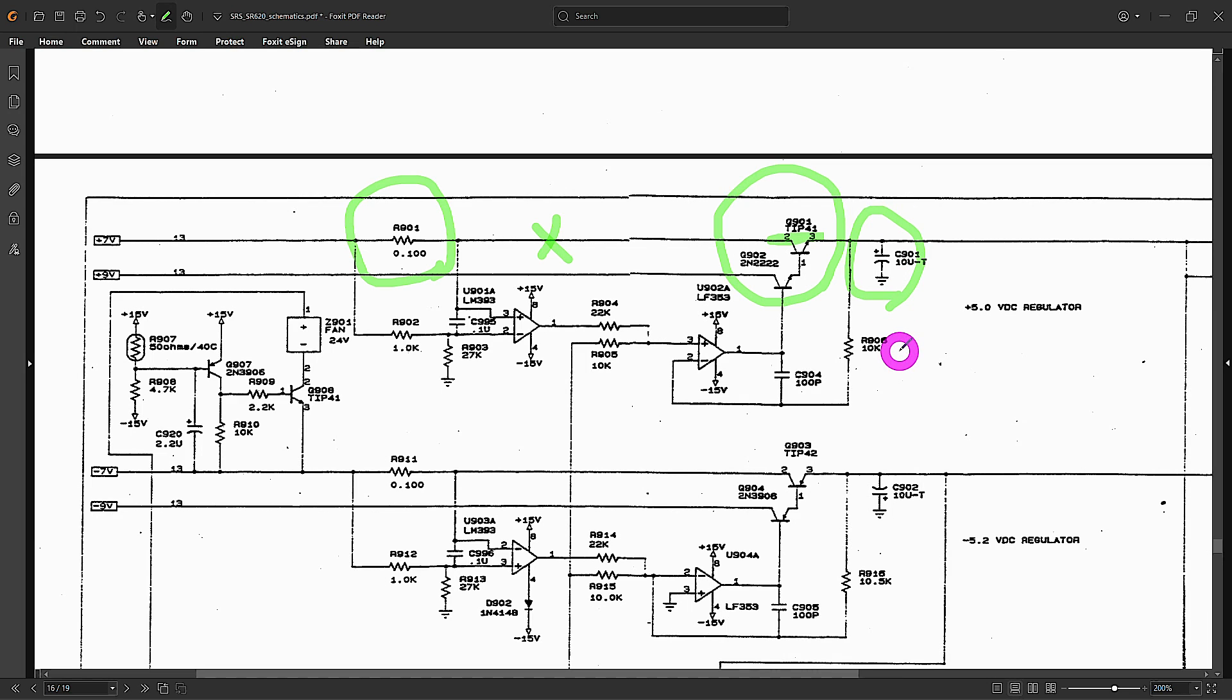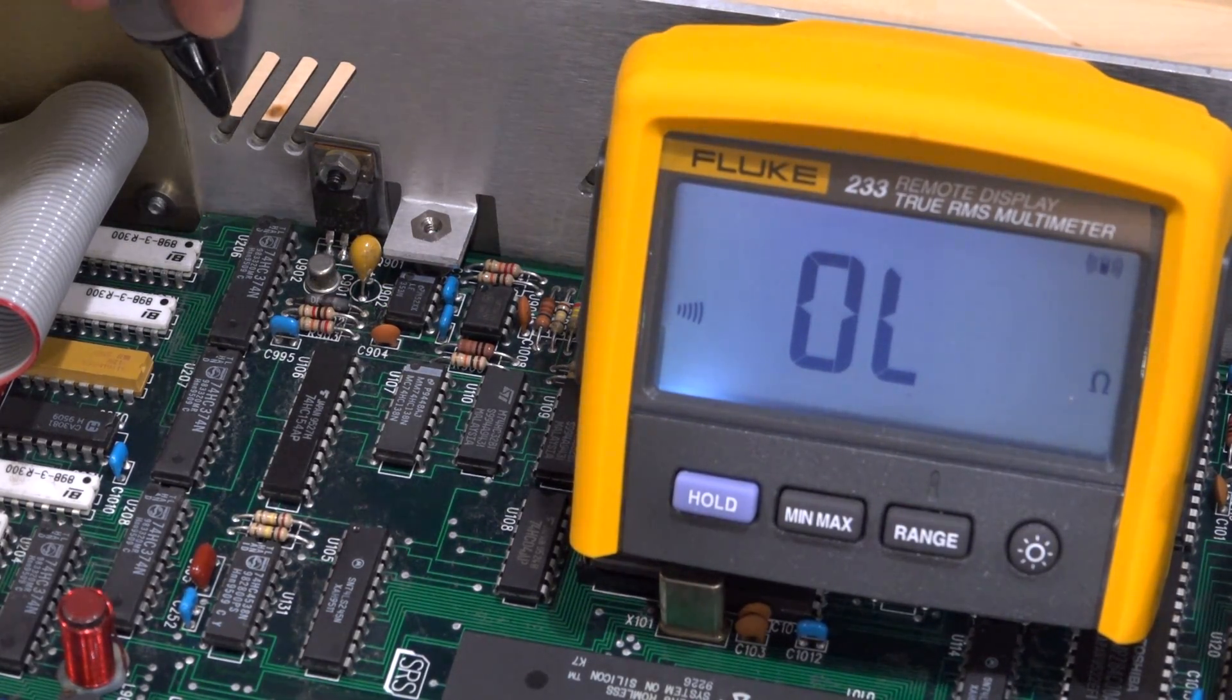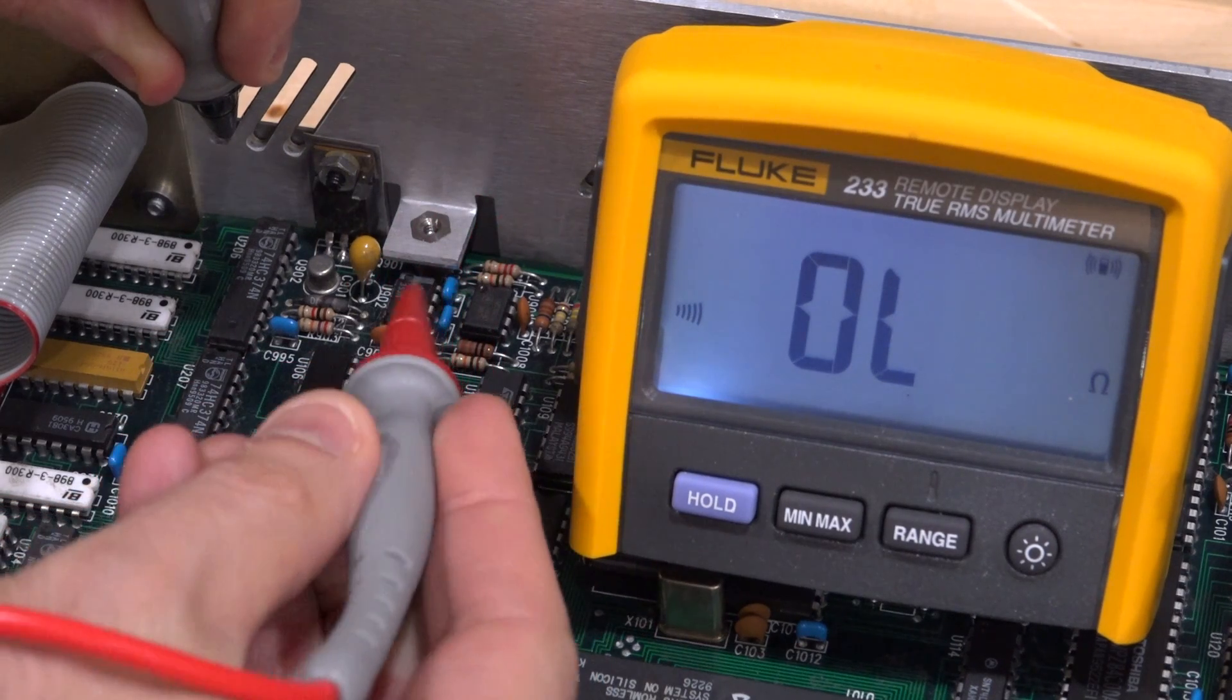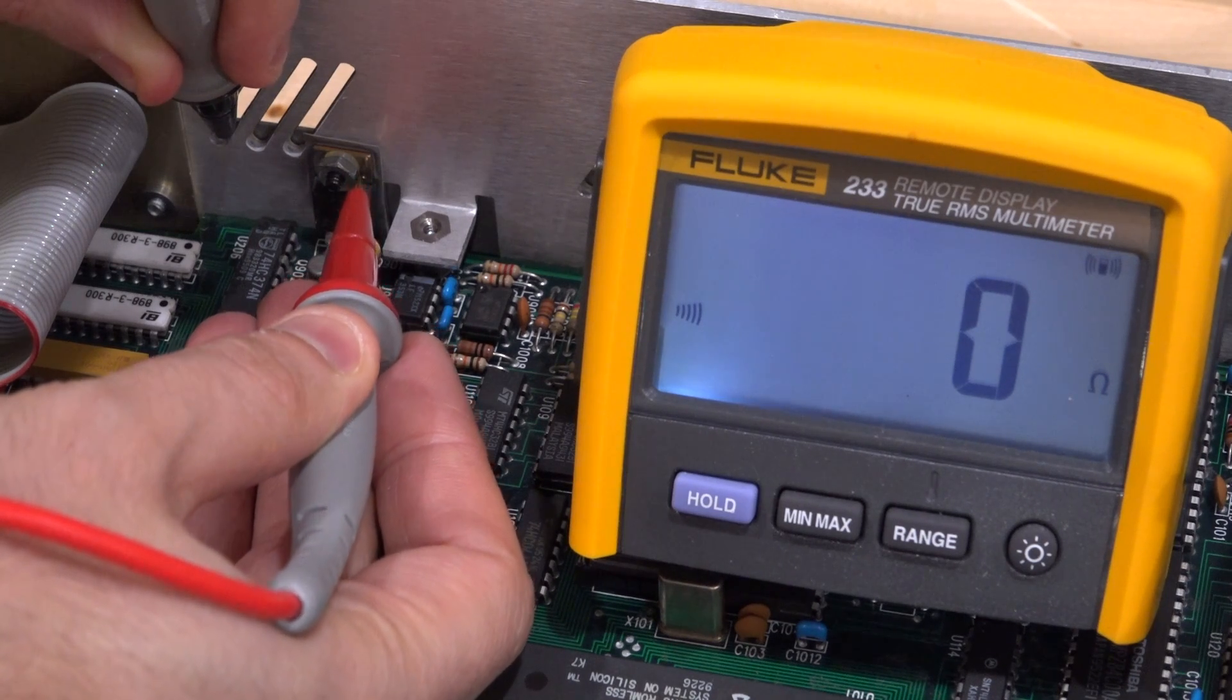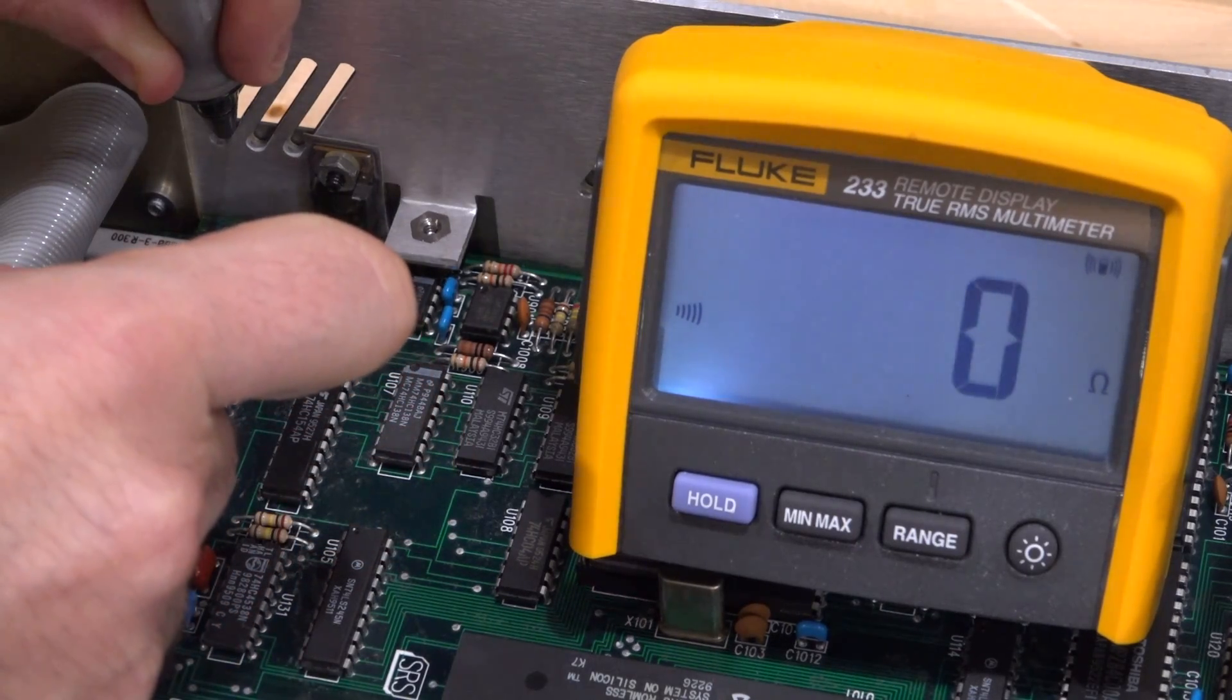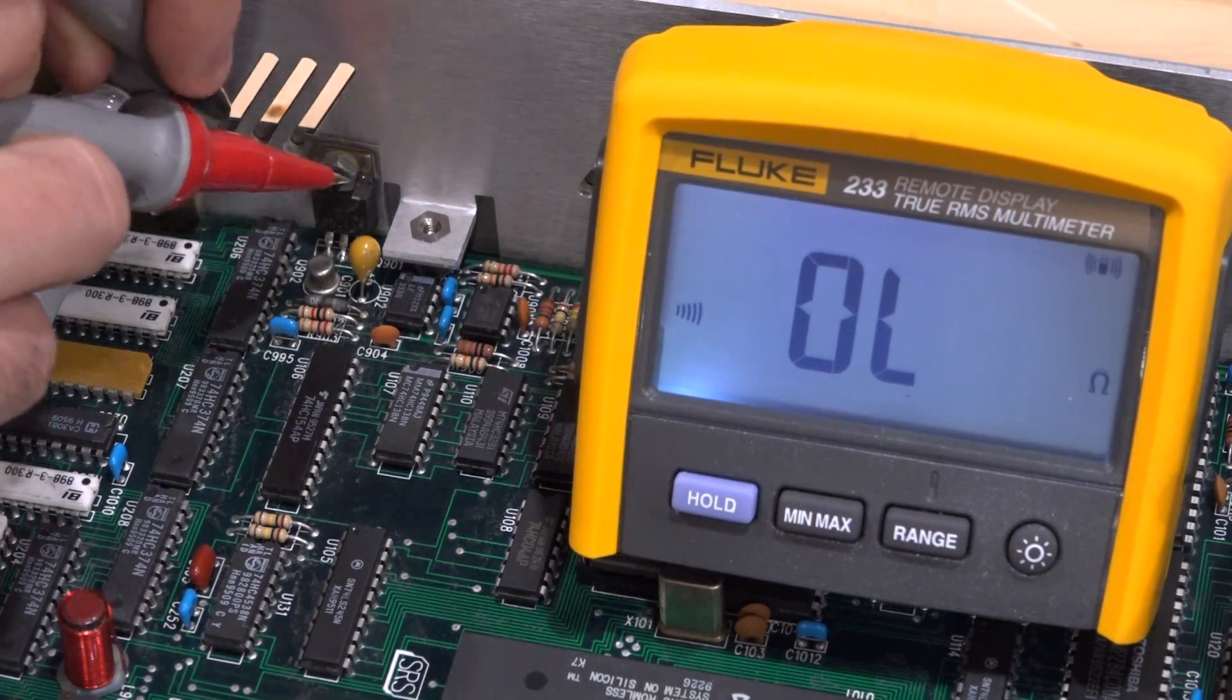But a short circuit can only happen if somehow there is a ground introduced somewhere. This could be shorter I guess potentially speaking, but the other thing is that this is connected to the body of the instrument and I wonder if that's what has happened. If a failure has happened at that point causing one of these terminals to be shorter, that could explain it. So now we have enough knowledge from the schematic to go back and take a look and do some quick measurements. Okay, let's see if our hypothesis is correct. Here I'm going to use one terminal of the multimeter to the body of the instrument, which I suppose is ground. So you can see the body is ground. And we will hear that I'm going to go to this body of this transistor, and look at that, that's grounded. That shouldn't be grounded, that should be isolated from the chassis. So if I go to one side of the resistor, therefore, yep, I measure zero ohms. There you go. That explains it.